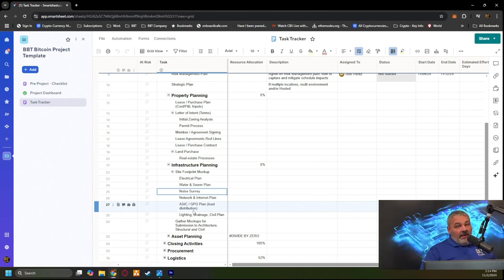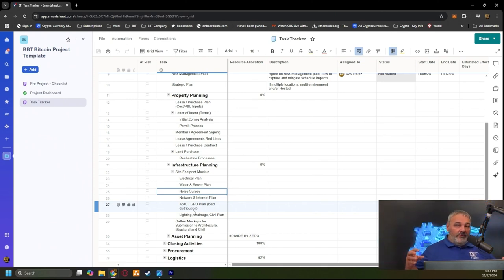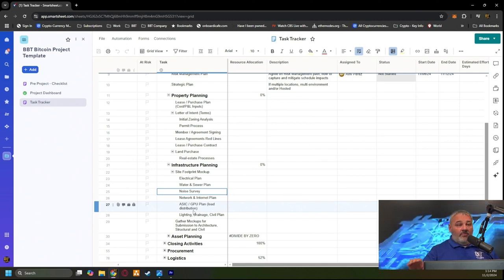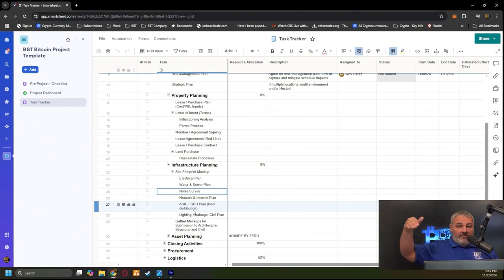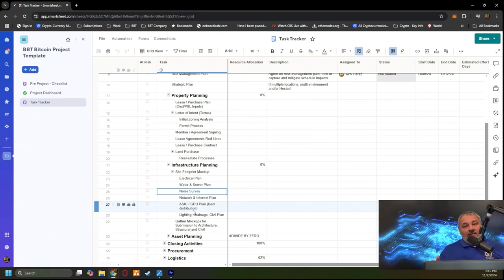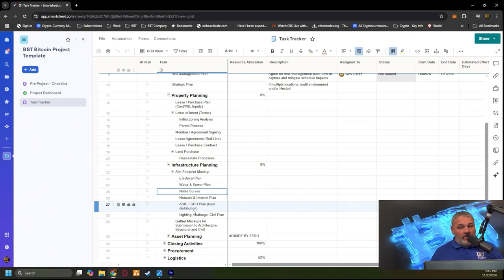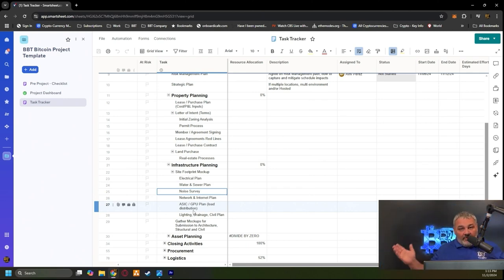For a load plan, say on a 5 megawatt building, you might have two 4,000 amp primary cabinets bringing in 2.5 megawatt services from 2.5 megawatt transformers. That twin 4,000 amp setup feeds into 8 per 4,000 amp service, 630 amp breaker setups—stepping from the secondary on the transformer to a disconnect, then to the 4,000 amp service, then to 8 separate 630 breakout panels. Those then go to your various PDUs. Each 630 gives you about 90 miners of constant load up to 4,400 watts, running at about 75% load factor continuously. So 4,000 down to 630 amp, totaling 16 of those 630 amp setups.